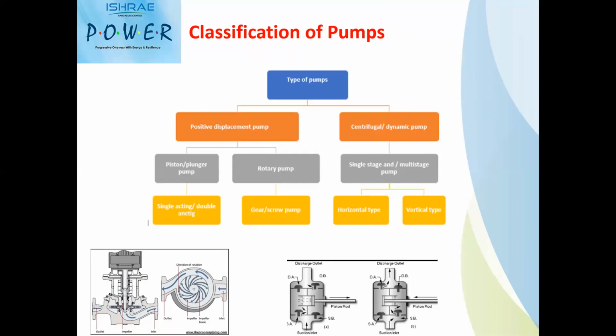In case of centrifugal pumps, again, we have single stage and multi-stage pumps. In 99% of our HVAC industry, we use single stage pumps, where you will have a single impeller in the pump. Multi-stage pumps are used for high pressure applications like our plumbing pumps, wherein you need to create pressure in the water. And then in case of centrifugal pumps, we have horizontal design pumps as well as vertical type design pumps as well. I think you can see my cursor. This is a centrifugal pump where the water enters from the axial side and creates pressure by centrifugal action. These are the positive displacement pumps where the liquid is pushed by a piston like this from one level to the other level.